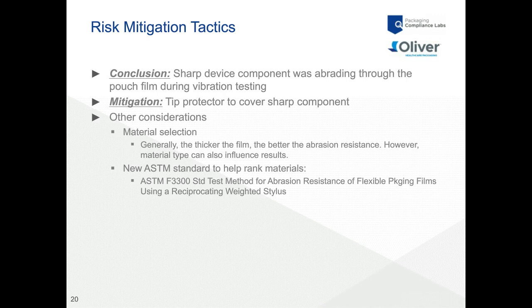Think about that — as mentioned, a total of roughly 4 hours on the vibration table. Think about the number of cycles of the device rubbing against the package, and the package rubbing against the sidewalls of the carton. It really tells a story. In this case, we concluded again that it was that sharp component within the medical device that was abrading through the pouch film. The mitigation was to put a simple tip protector over that component — it seemed like the safest route for the customer, so we were able to do that.